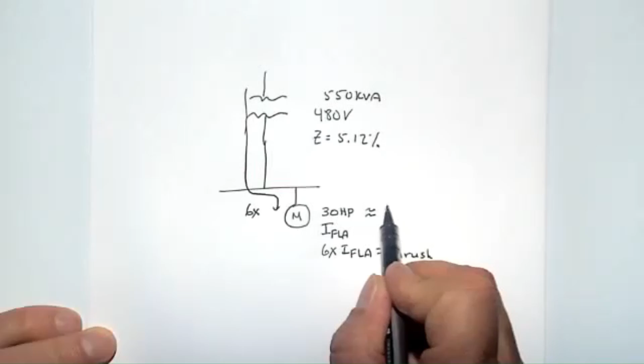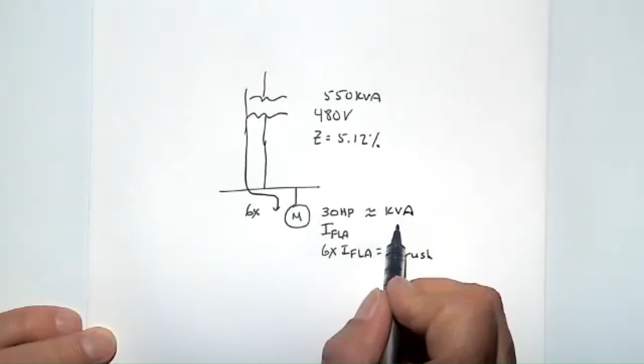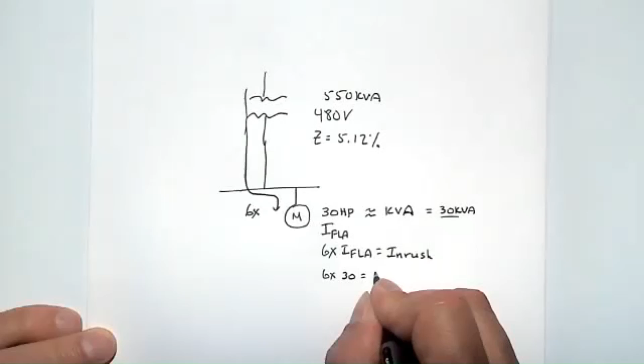Now, what's interesting about that is horsepower is just about equal to kVA. If you do the calculation and take out the efficiency and the power factor and everything, you end up finding out that horsepower is about equal to kVA. So we have about 30 kVA of normal load. As we look at inrush, then our inrush is 6 times our normal kVA, which is 30. So 6 times 30 is 180 kVA inrush.